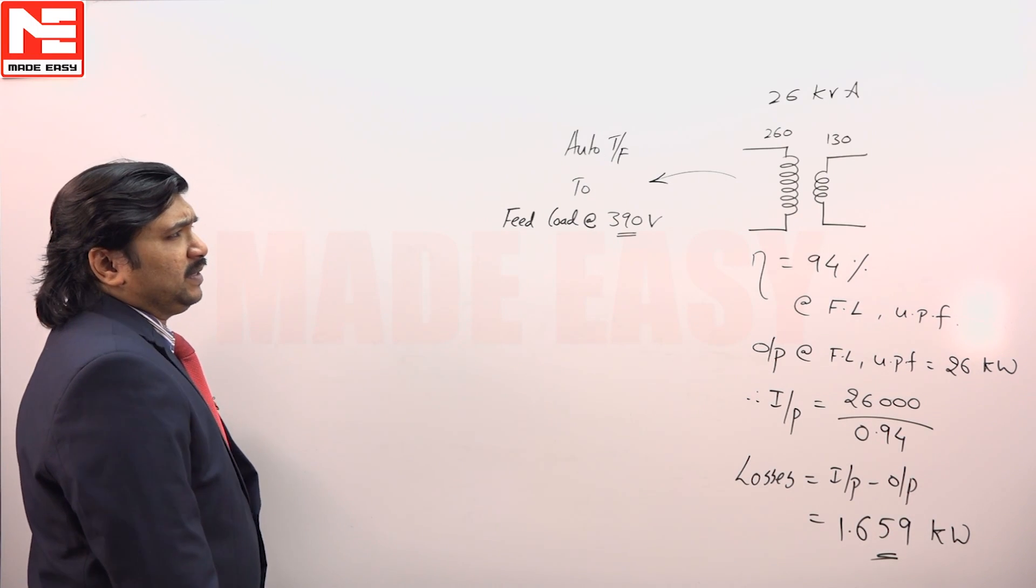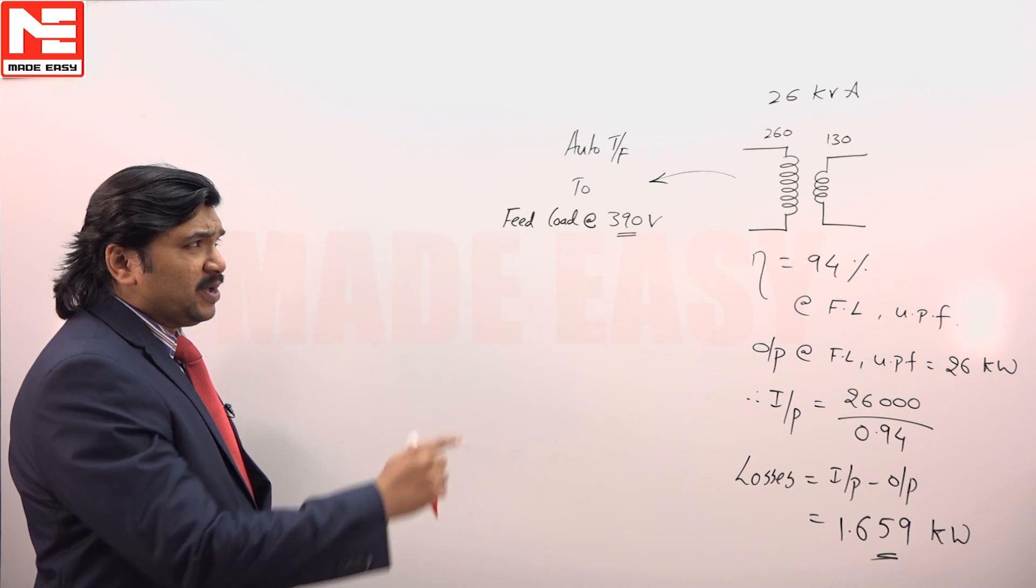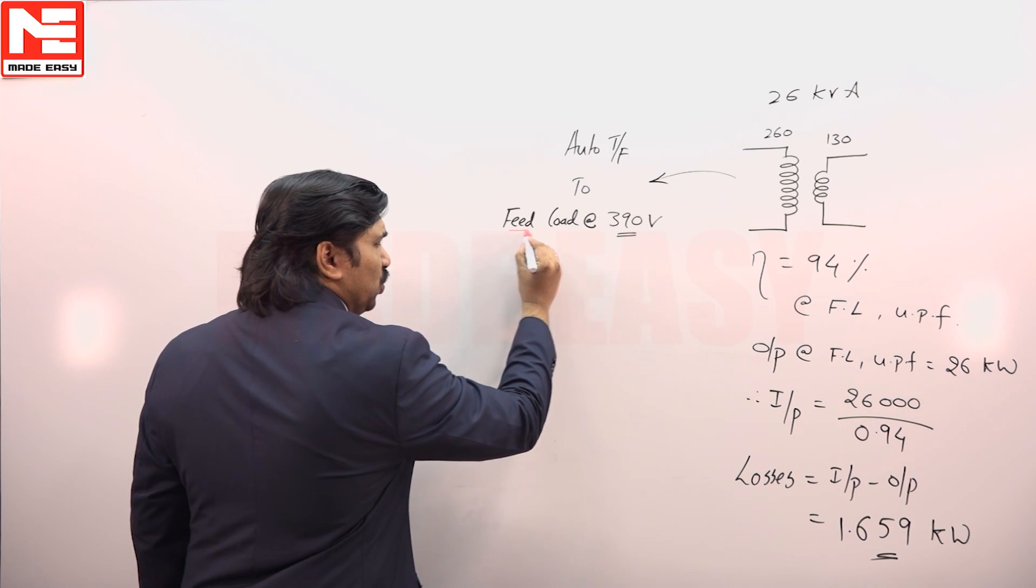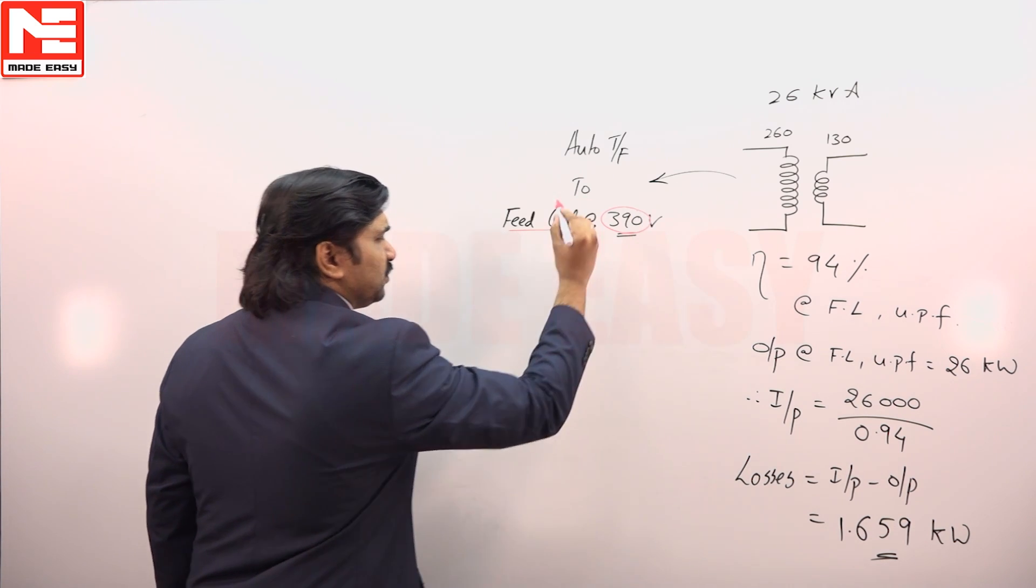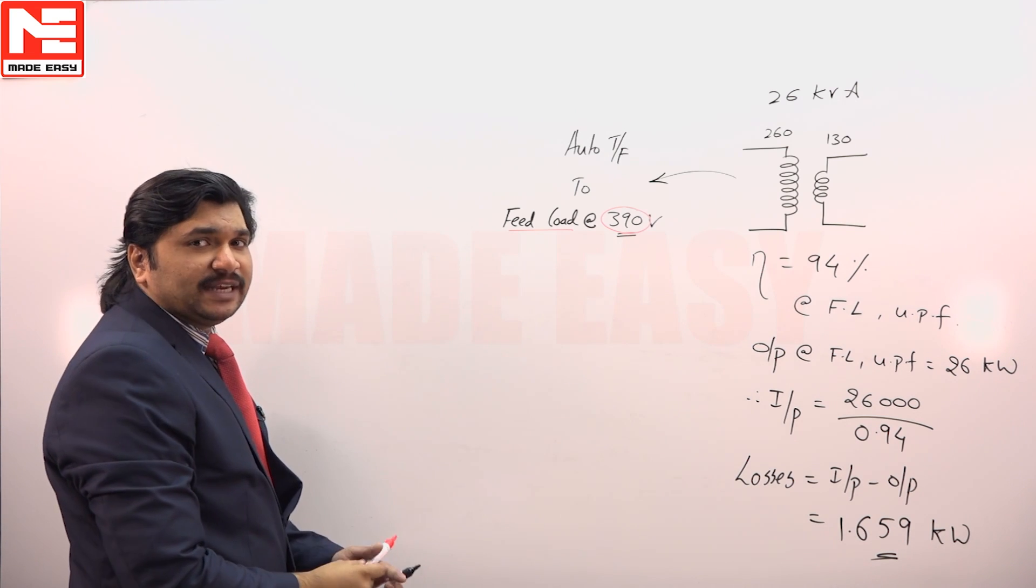This question was given like a 26 kVA 2-winding transformer is reconnected into an auto transformer to feed a load at 390 volts, which means definitely it should be connected into additive polarity.